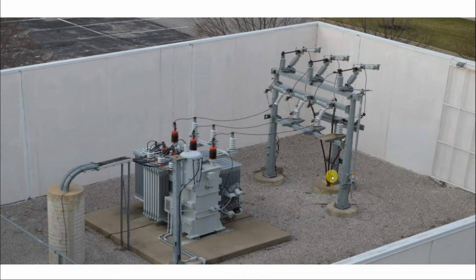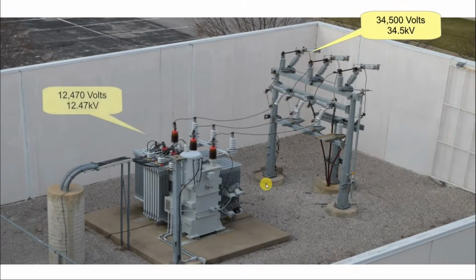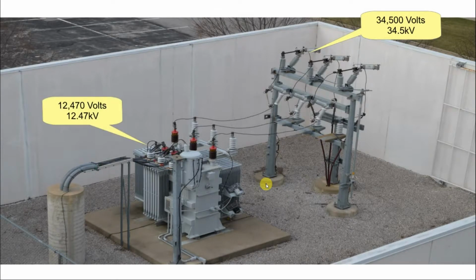That 34,500 volts you saw go into the ground comes up right here and gets distributed to a step-down transformer, which takes the 34,500 volts and steps it down to 12,470 volts. There's also switchgear here that lets the utility disconnect us from their service right inside this substation. This transformer is oil-cooled, and you can see fans here that blow on it.